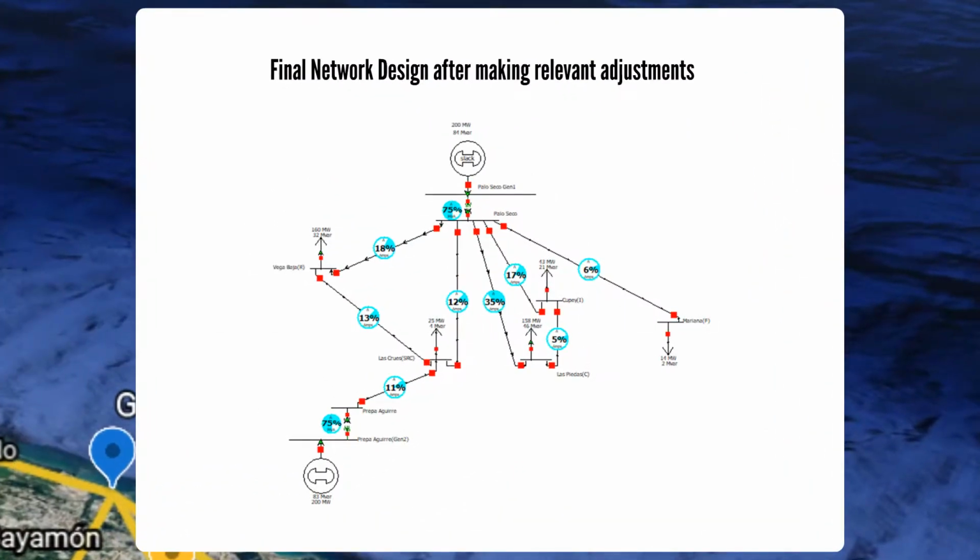Another constraint in the lab involved us not loading our transformer above 75% of its capacity, bearing in mind that the maximum load that can go on the system is actually 500 megawatts. So this diagram merely shows the output after the parameters were changed to facilitate the constraint of the transformer in our lab design exercise.